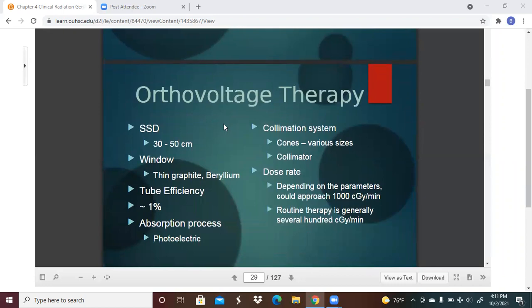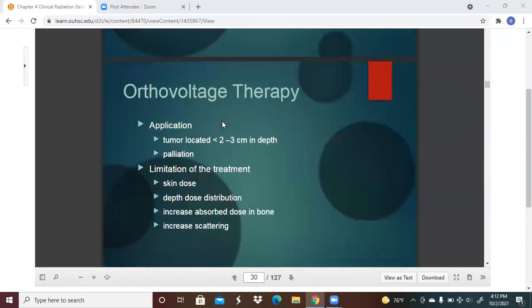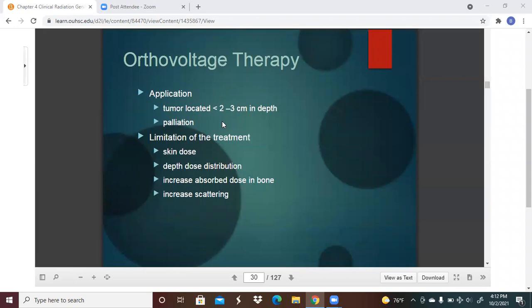For orthovoltage therapy, the SSD is anywhere from 30 to 50 centimeters. The window is going to be thin graphite or beryllium. Obviously, your tube efficiency is roughly around 1%. Absorption is going to be photoelectric. Collimation system: cones of various sizes. The dose rate, depending on the parameters, could approach 1,000 centigray per minute, and routine therapy is generally several hundred centigray per minute. The application: the tumor is located less than 2 to 3 centimeters in depth, normally for palliation. The limitations of the treatment are skin dose, depth dose distribution, increased absorbed dose in bone, and increase in scattering.